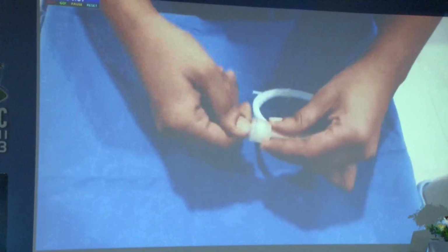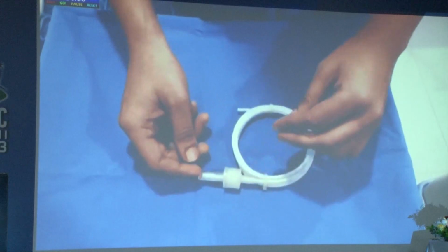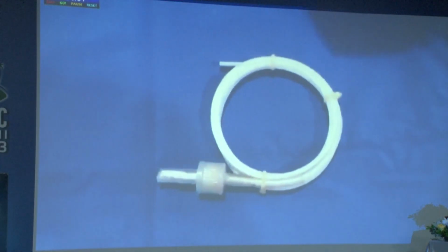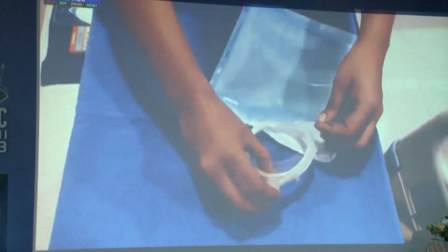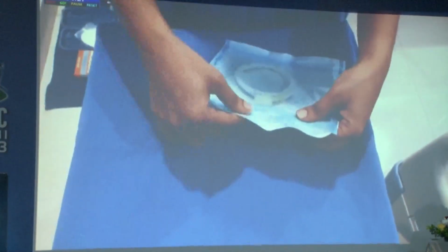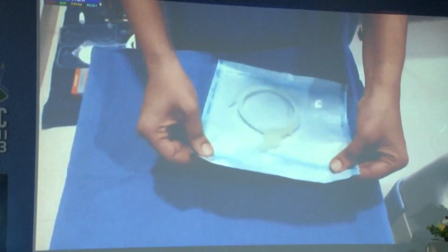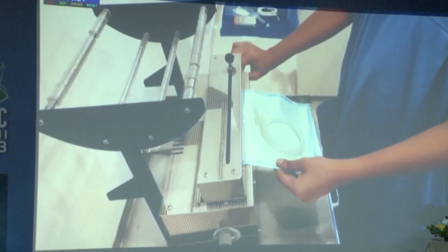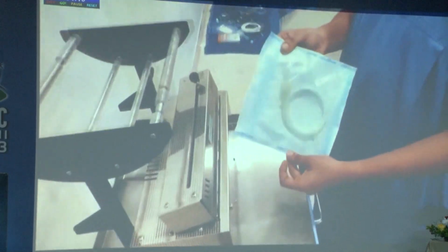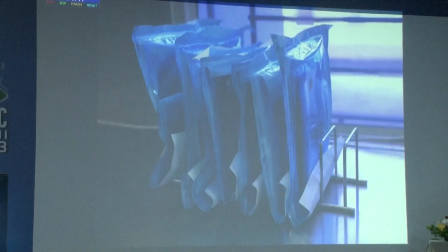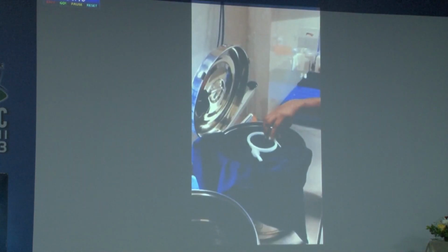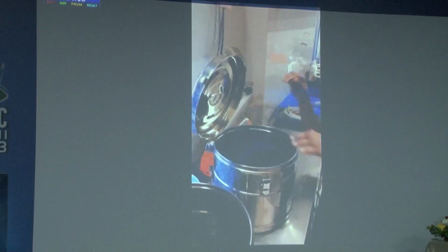This is simply based on the principle that your autoclave should be efficient enough to remove the air first and then has the adequate pressure to push the steam inside this series of tube to reach the indicator on the other side. Again, pack it exactly the same way as you pack your phaco set and the other instruments. And then place it exactly the same way you place your instruments. So you're actually simulating exactly the same demanding technique for your instruments also.